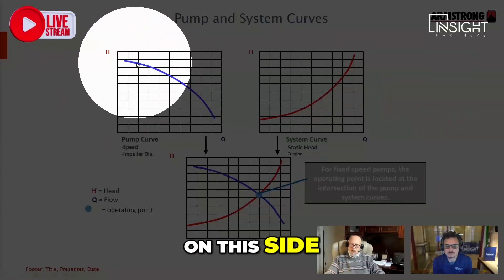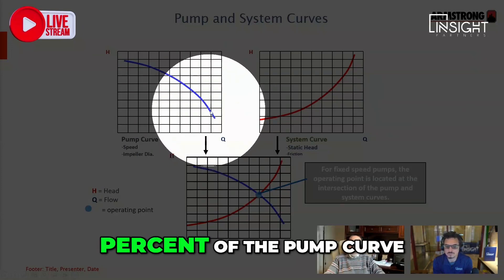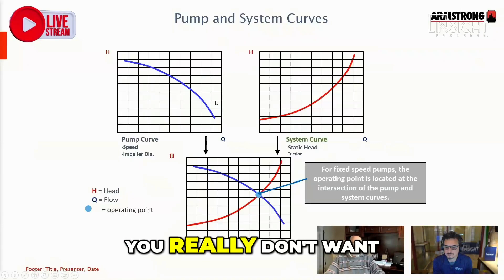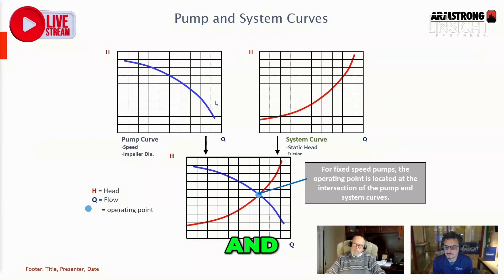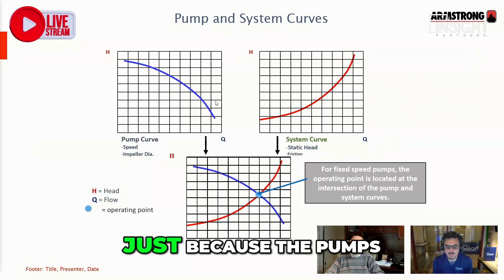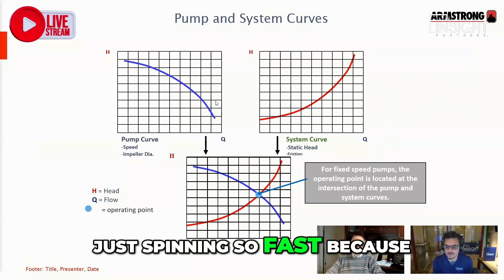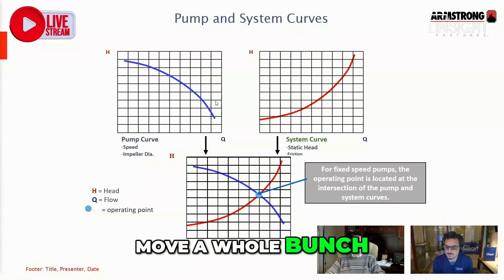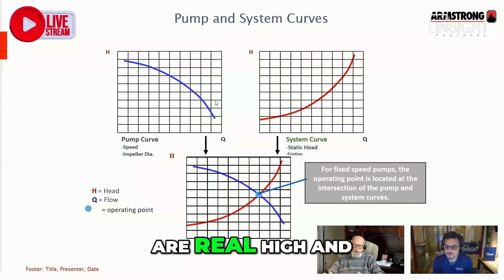So we go from over here, and this is known as shutoff head on this side, and this is known as runout. Once you get out in this last 10%, 15% of the pump curve, you really don't want to run there. You start to get into the unstable region of the curve. You really don't want to be running out in that range. Is this because the pump's just spinning so fast because of lack of pressure? Yeah, the pump is trying to move a whole bunch of water, and the velocities are real high.